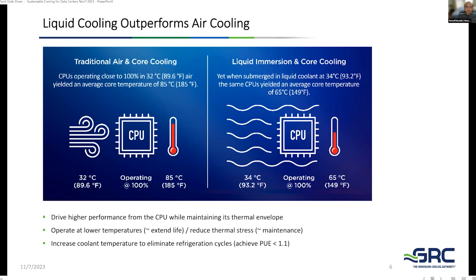So if you look at the next slide, in a traditional air cooling environment, if I put a chip, a CPU, I provide air at 32 degrees Celsius, it will operate at close to 85 degrees Celsius. Now, when I use a different medium called a single phase coolant or a liquid, I provide that medium at 34 degrees Celsius, 2 degrees higher. But we find that the chip temperature doesn't exceed 65 degrees Celsius. Now you will say, how does this happen? This happens because the medium that we use is 1000 times more thermally conductive than air.